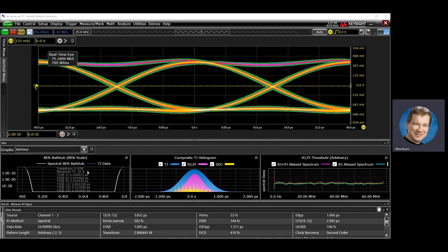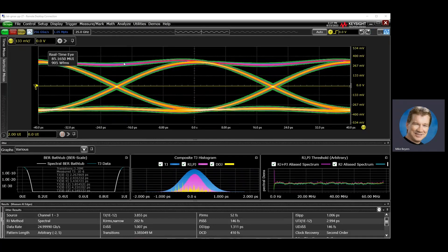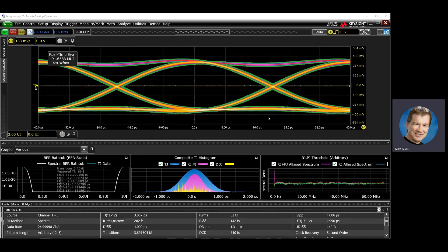Now, notice that while I'm analyzing 2 to 3 million transitions down here, I've plotted 77 million UIs up top. That is quite a bit more data in order to see truly transient-type events. The new NRZ contours can help us analyze the more information that's up here.